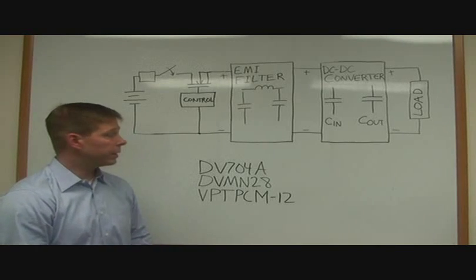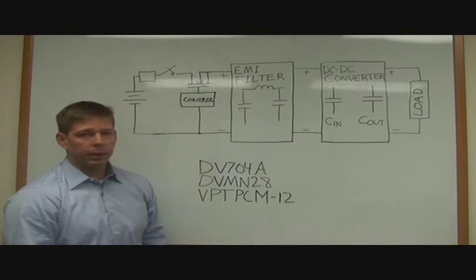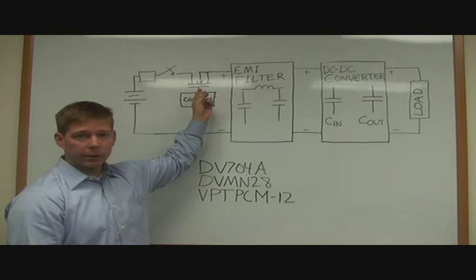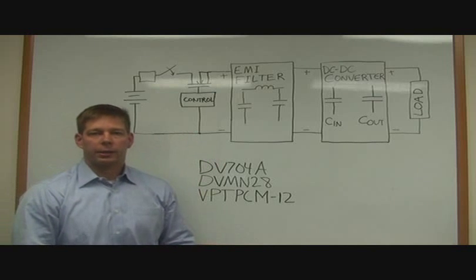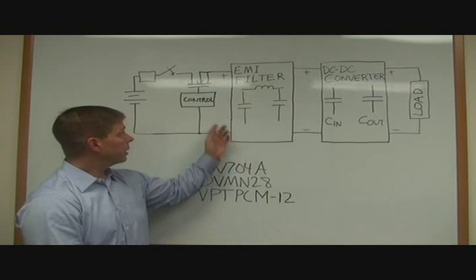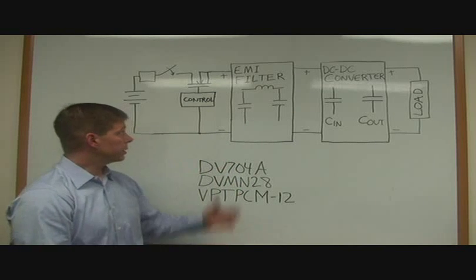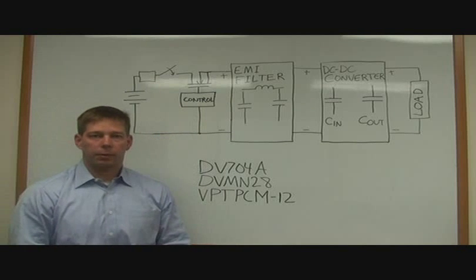The customer can also easily implement inrush current limiting with a series switch in line with the input. The switch can be either in the positive leg or in the ground leg. Basically, the control circuit acts to slow down the voltage rise time to the input of the EMI filter and the DC-to-DC converter. This is basically what's implemented in these three products to limit inrush current.